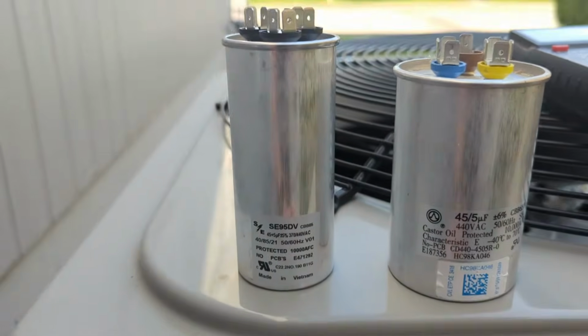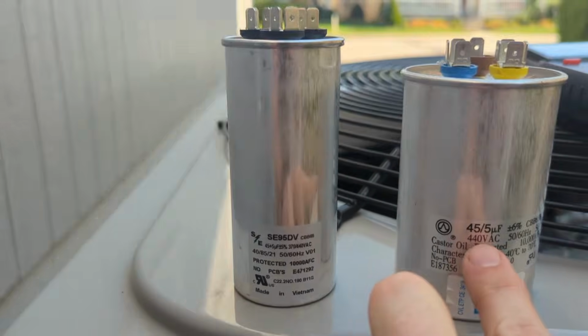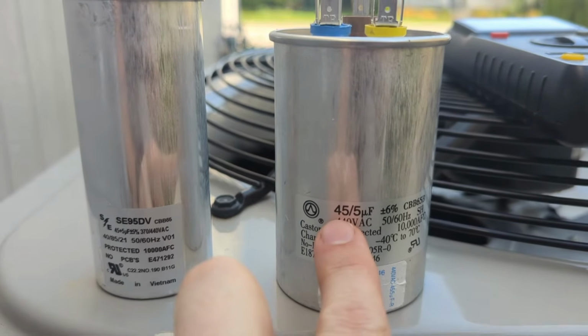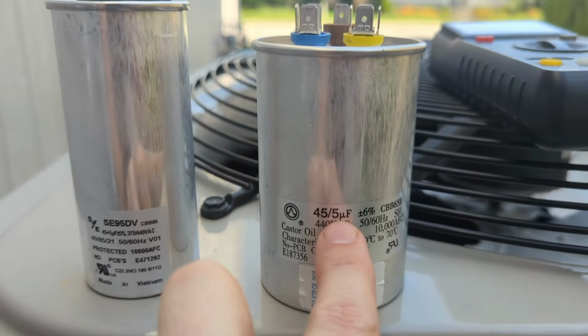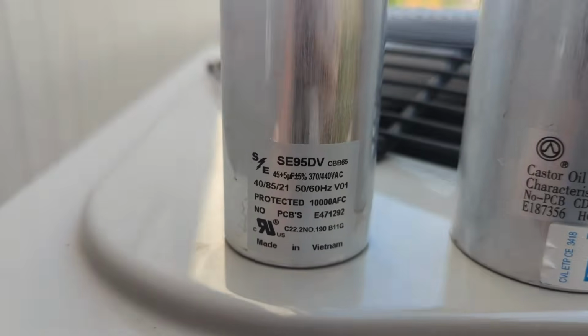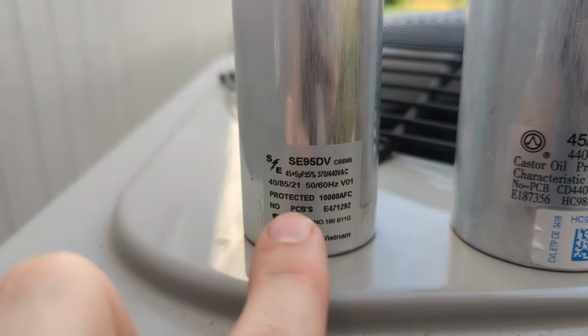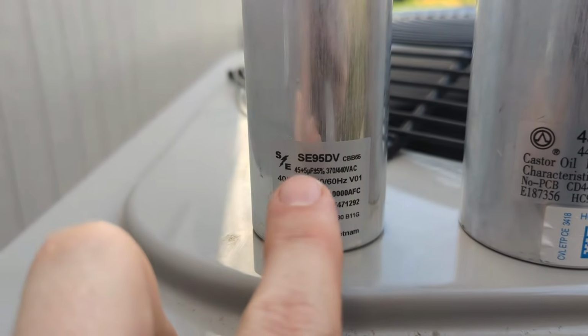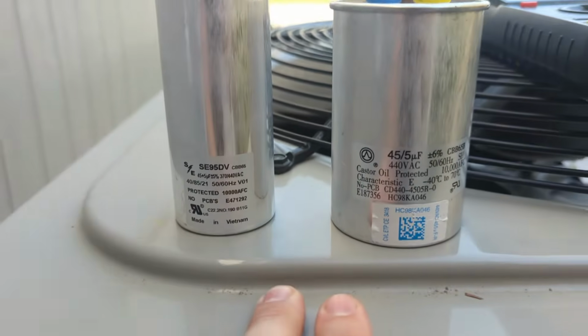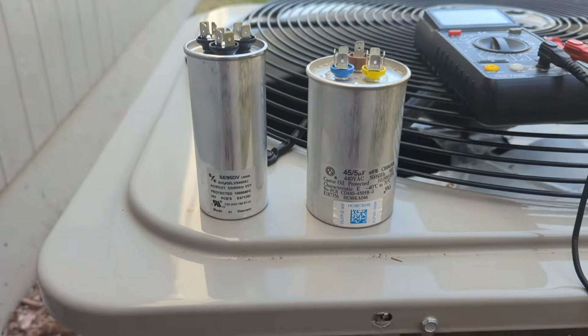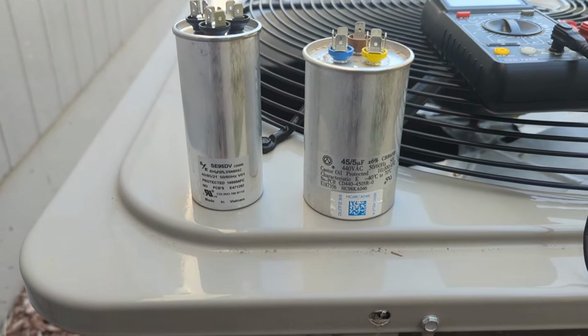What's most important is that these numbers match up. So you see here, 45.5, that means 45 microfarads for the compressor, 5 for the fan. Same over here, you've got 45.5 and 440 volts AC, 440 volts AC. So they're the same juice inside. They're just a little different shape, and that's okay.